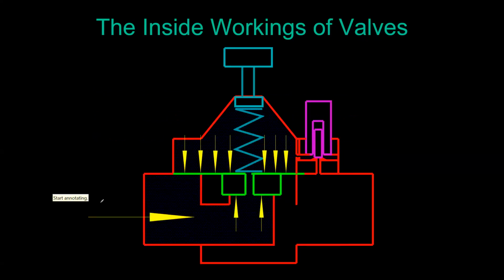Okay, so the valve is always under pressure. The water's always in here, and it's always trying to push the diaphragm up. The diaphragm is this green part here. So it's always trying to push up on the diaphragm, but there's also water in the top chamber of the valve pushing downward. So there's more surface area on the top here, the same pressure that holds the diaphragm closed against this seat. Here's your solenoid, and that's just a little electromagnet that lifts this plunger up and then lets it drop back down when it's done running.